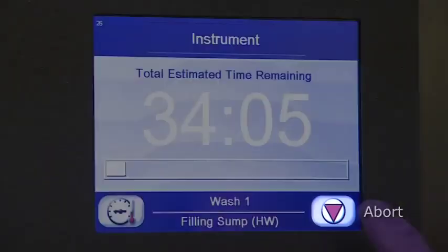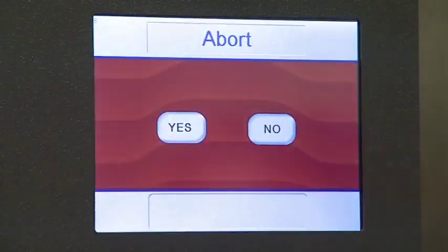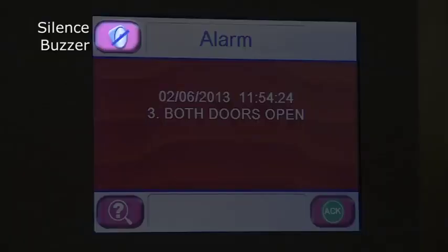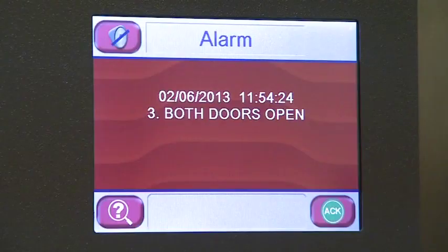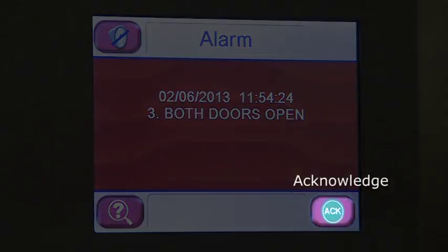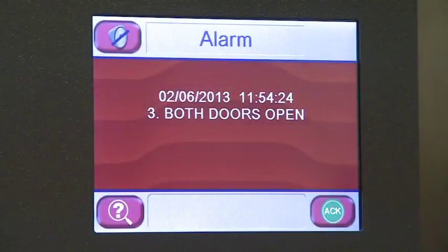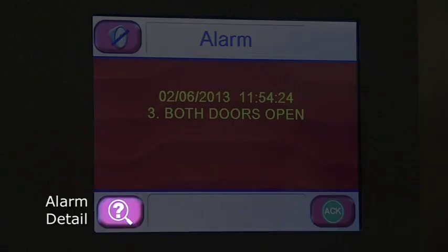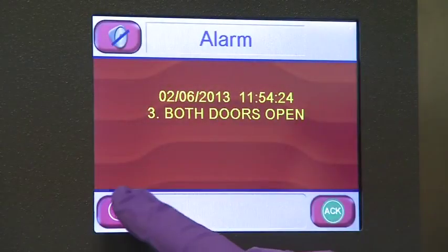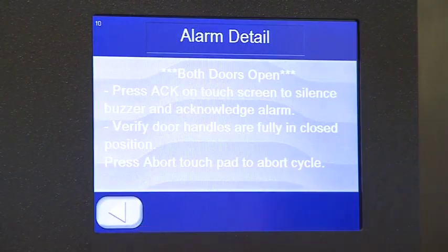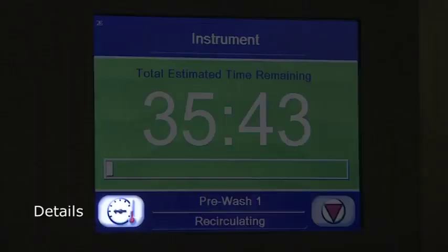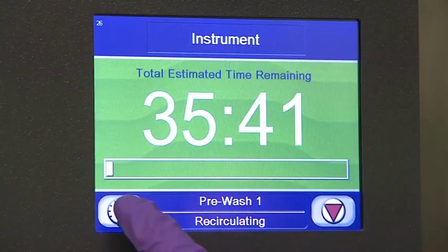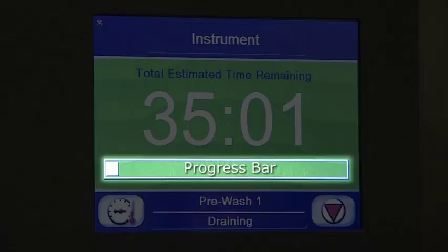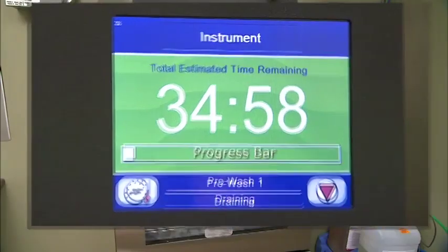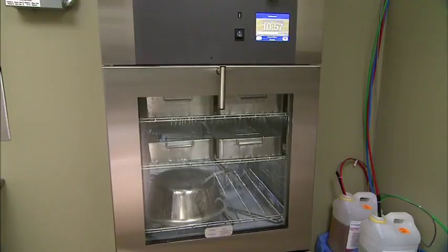Abort. Press Abort to interrupt cycles. Silence buzzer. Alarm buzzers can be stopped by pressing this button. Acknowledge. This button stops the alarm buzzer and acknowledges the displayed alarm message. It also confirms entry. Alarm detail. Press this button when you want to see more information about the alarm cause and corrections needed. Details. Press this button to view current cycle data parameters. Progress bar. The progress bar is displayed on the chamber screen to show the cycle progress.